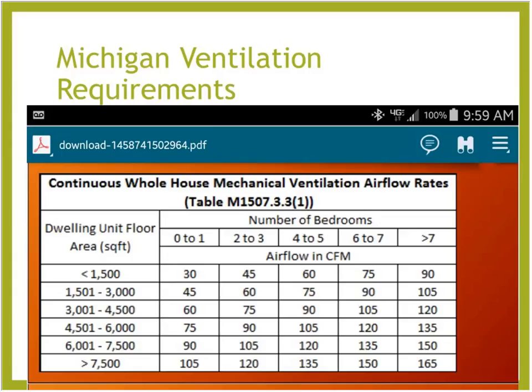But over that period of time, we've also introduced a tremendous amount of chemicals, a toxic soup, if you will, into our homes, from cleaning supplies and fabrics and fabric protectors and all of this type of stuff, paints and varnishes and glues and solvents, things that we know independently what their health risks are, but we've never done any evaluations of what the overall health risk is of this chemical soup. And so mechanical balanced ventilation systems are extremely important. I look at the overall life cycle cost of ventilation as being the initial upfront cost, and then the operating cost, and then the energy cost of reconditioning air that's being taken in against the air that's being lost, and then the health costs that are all added onto that. So this is one of the most critical aspects of the new code.